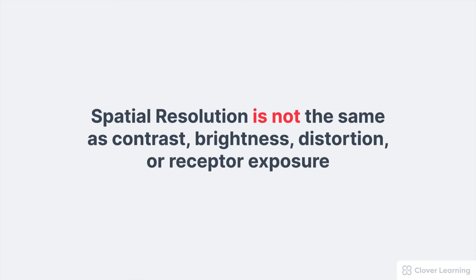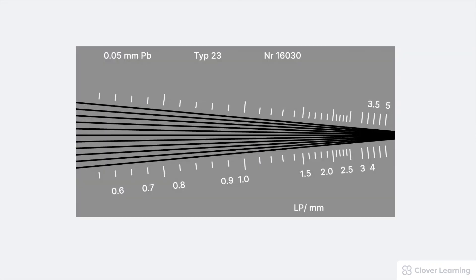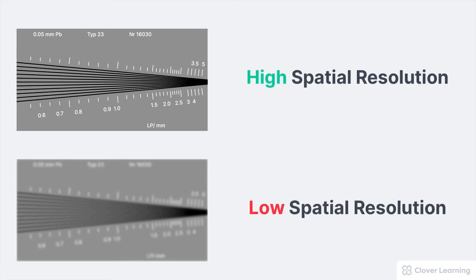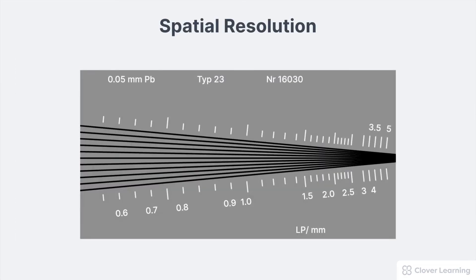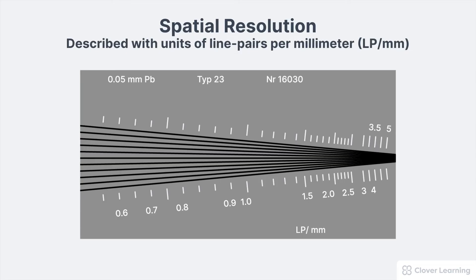Spatial resolution is its own quality factor — it's not the same as contrast, brightness, distortion, or receptor exposure. It's important for x-ray equipment to produce detailed images of small parts. This is actually tested using a tool called a line pairs device. The tool has several small line pairs placed close together, and as the lines converge, they get smaller and closer together. The smallest lines that can be visualized on the image represent the spatial resolution of the image. The upper image has a superior spatial resolution because smaller lines can be distinguished from each other. So radiographic spatial resolution is described with units of line pairs per millimeter.